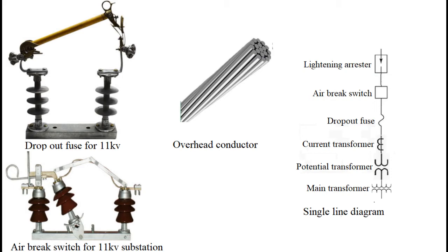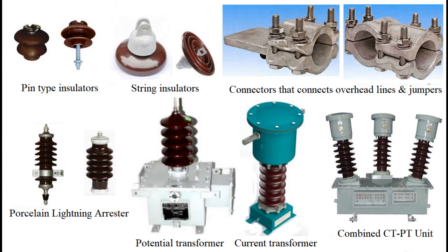A plinth is a concrete foundation to keep the transformer, used with rollers so that the transformer may be easily shifted and moved from an existing location to a new location. If the transformer is plinth mounted, then a structure is used to rest the incoming 11 kV lines, using pin type and string type insulators for each phase of the line.